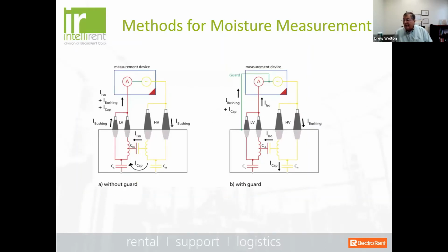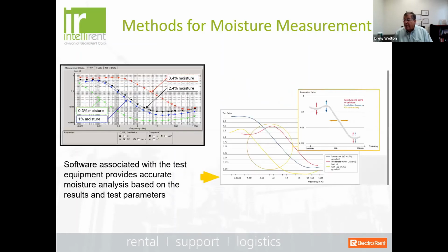Okay, so this is kind of a connection diagram. It's a loaded device where you will tie your bushings together to simulate the load, and then you have your low voltage cable along with a guard to keep any noise, if you're in a noisy substation, from interfering with the test and the test results. So we're just going to inject the frequency signal at around 200 volts on the high side and measure on the low side, and come up with our measurements. And this is what you'll see as a result.